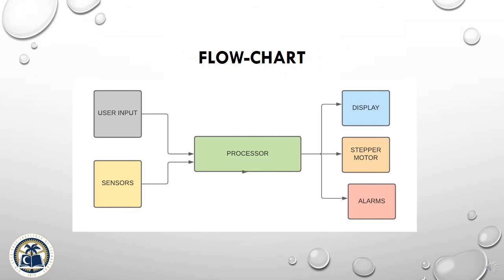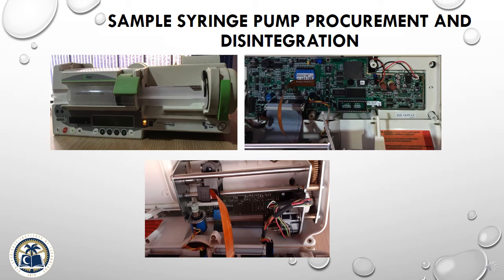This is the flow chart explaining the working of a syringe pump. In this flow chart, it is shown that the user puts an input and sensors also, and the data from the sensor also acts as an input, and the processor then processes it and gives output in the form of a display, movement of the stepper motor, or an alarm. We also procured a syringe pump and disintegrated it to get information on the components and design of the syringe pump. And these are some pictures of the syringe pump that we have procured.